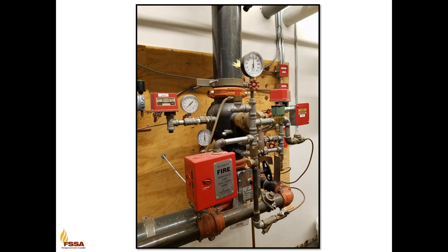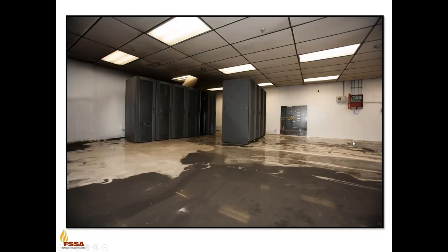Now you have a standard sprinkler system, ready to be activated when the heat of a fire fuses or opens a sprinkler head. It is important to understand that there is no increase or decrease in the level of protection with a pre-action sprinkler system. A pre-action system simply provides assurance that there is no water in the pipes above that could possibly leak, causing damage to the high-value assets below.